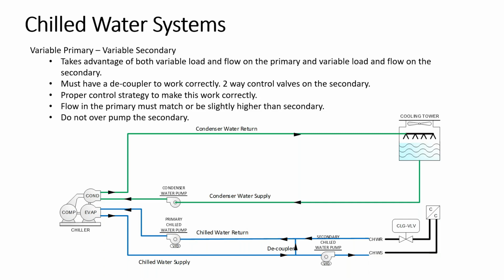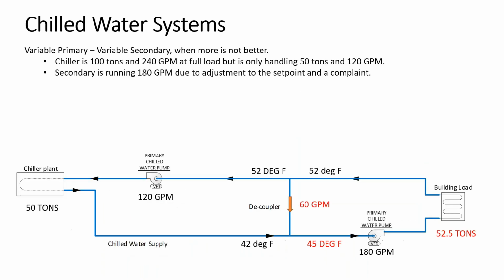You have to have a proper control strategy though to make this work. And the primary flow must match or be slightly higher than the secondary. Do not overpump the secondary, and that's where we run into trouble. We see this a lot. And here's an example. Here we have a variable primary running about 120 GPM. You've got a 10-degree differential across the chiller. It's running around 50 tons. Its design is 100 tons, so we're running 50 tons over here. It's half of the flow.